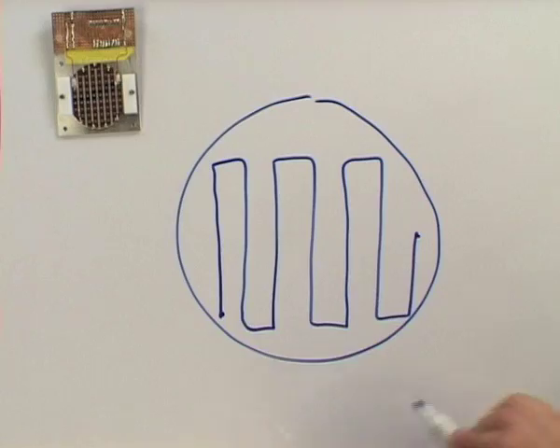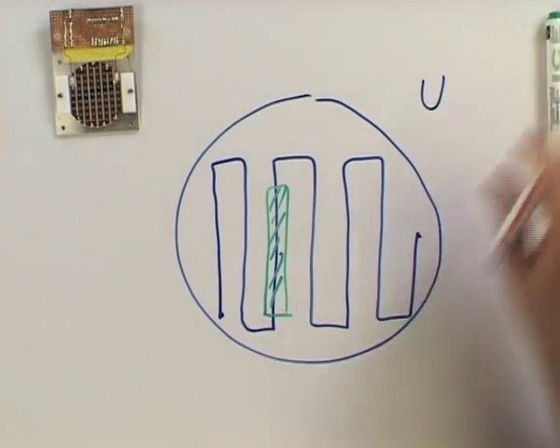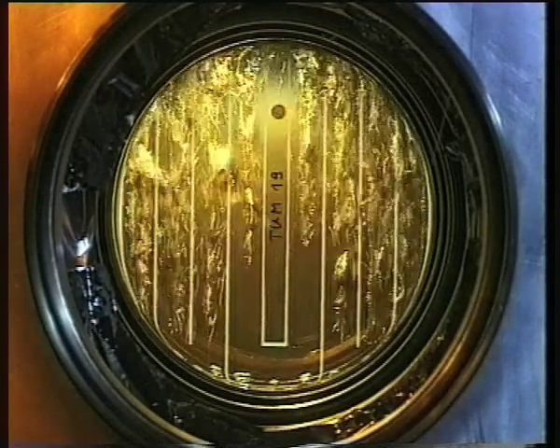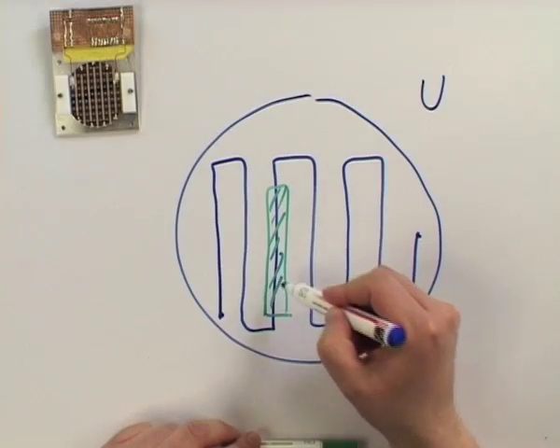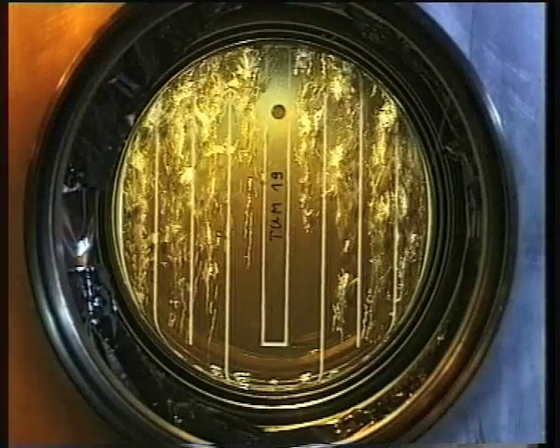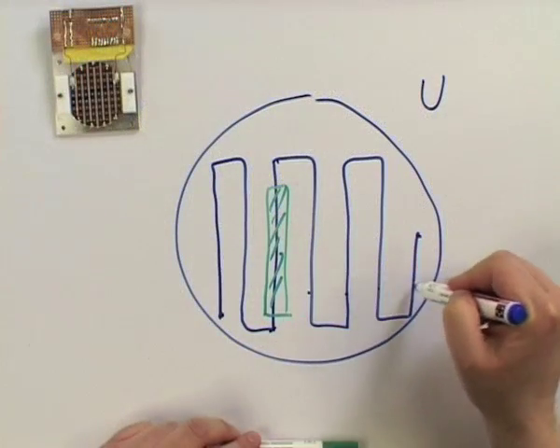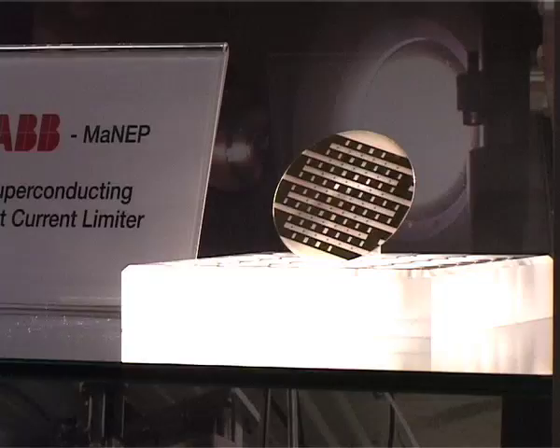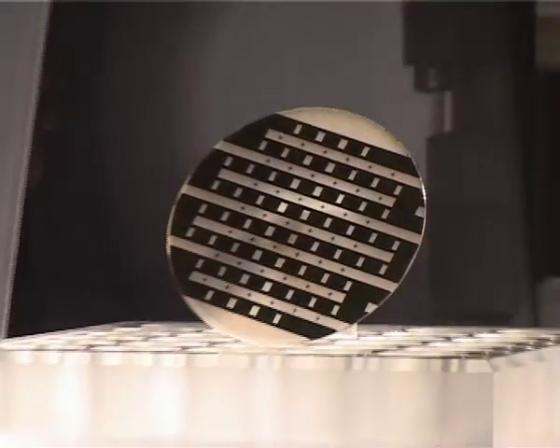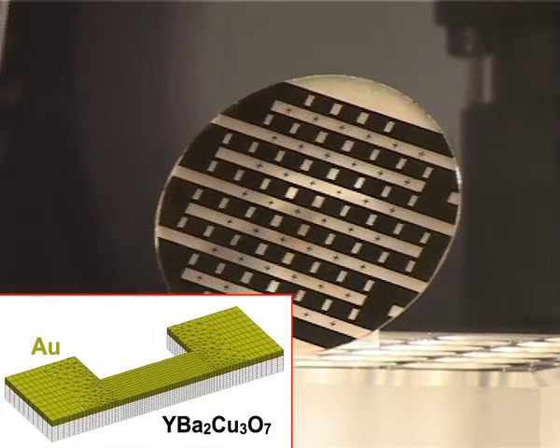When there is a short circuit, only part of the meander will switch at the beginning, which means all the power will be concentrated in that part of the wafer, and only that line is working as a full current limiter while the others are not. A thin-film-based fault current limiter on a two-inch wafer uses constrictions along the meander. These constrictions are placed in order to better distribute the power during a short circuit, which increases the performance of the thin-film-based fault current limiter.